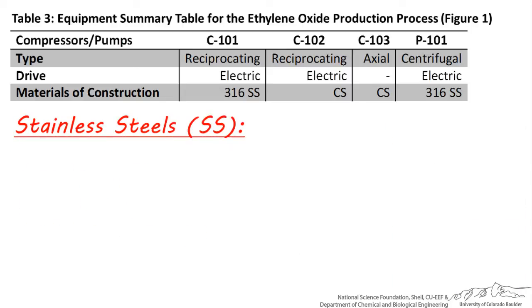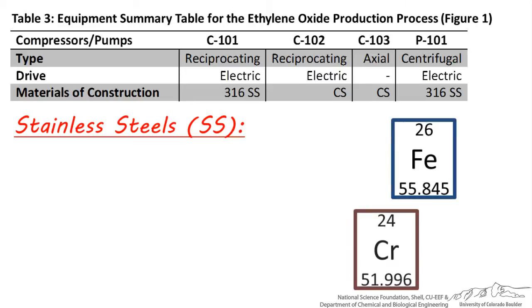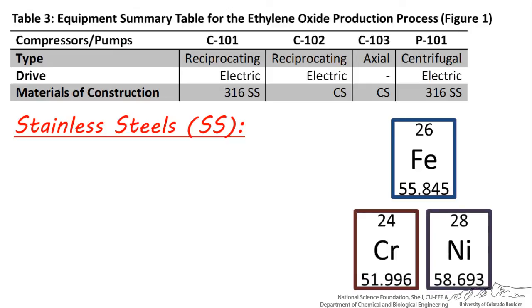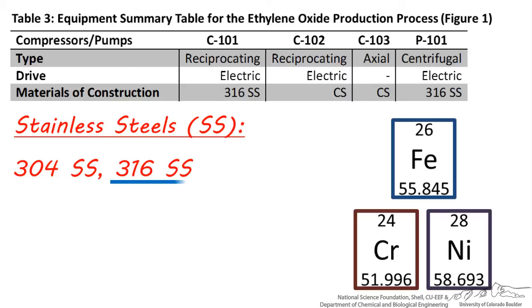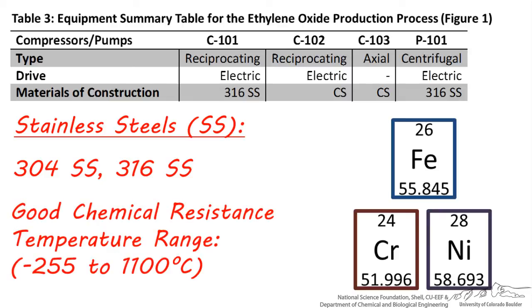Stainless steel, abbreviated SS, is a very common material used for process equipment, especially when minimizing contamination is a necessity. Stainless steel is mostly iron, with fairly high levels of chromium and nickel, along with manganese, molybdenum, and other metals and nonmetals. The two most common types used in process equipment are 304 — also called 18-8 stainless — and 316 stainless, both of which feature around 20% chromium and 10% nickel. These materials are used widely because they resist corrosion and reactivity with many acids and bases, so long as the concentration is not very high.